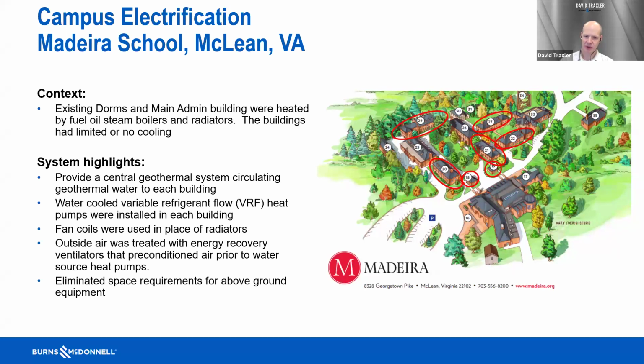Fan coils replaced the radiators in each dormitory, working out as a 1-for-1 swap in most rooms. Outside air was treated with an energy recovery ventilator so it could be heated or cooled with a traditional water source heat pump. These buildings had very small mechanical rooms, basically small boiler rooms and an adjacent space once used to store coal, later used for fuel oil tanks. We fit everything into the existing mechanical rooms with very limited disruption to the building floor plate, and it turned out really nice.